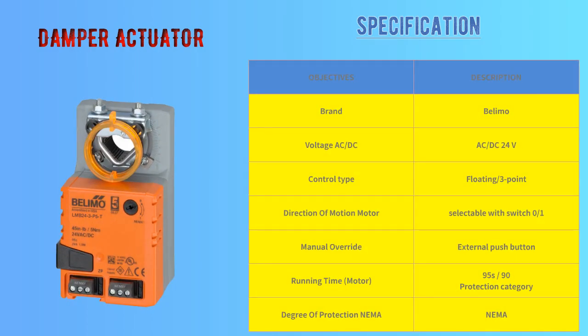Third, this is also a damper actuator, but the manufacturer is different — manufacturer name is Belimo. This is an on/off type actuator. As you can see, the control type is floating / 3-point: one point is for common, the second for open, and the third for close. These specifications I will discuss with you in detail in future videos.